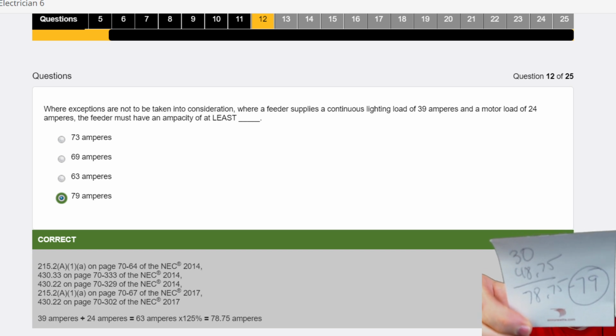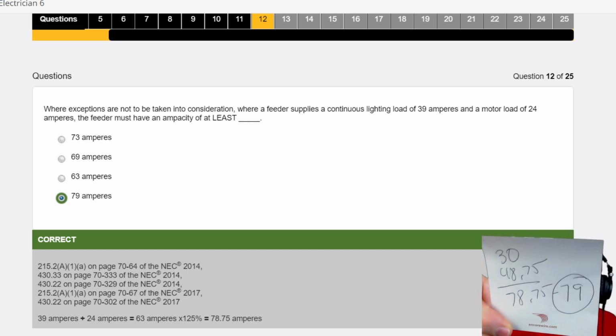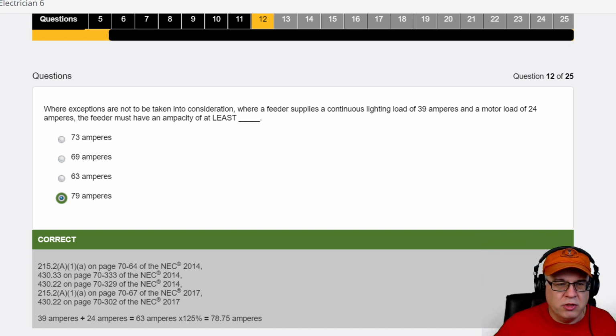See that? 30 and 48.75. So one way to do this is take the 39 at 125% and the 24 at 125%, or add them together and do them both at 125%. Same math, okay?